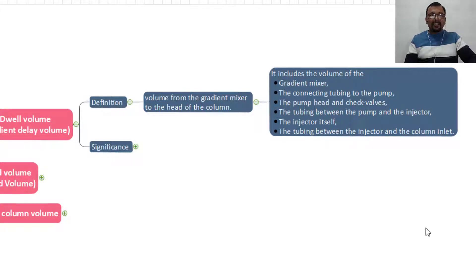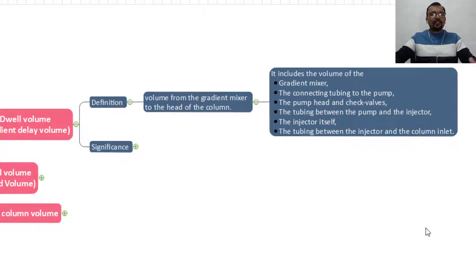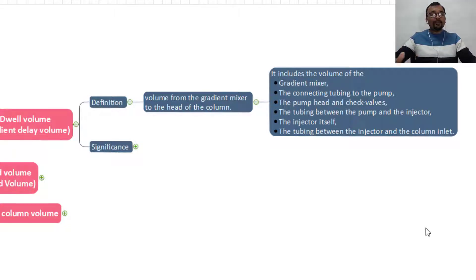The volume occupied by these different parts of the HPLC system are accountable for the dwell volume of the HPLC system. Generally, most laboratories nowadays have the quaternary system, and the quaternary system has a slightly higher amount of dwell volume compared to the binary system. The quaternary system can have a dwell volume of around 860 microlitres to around 1000 microlitres.